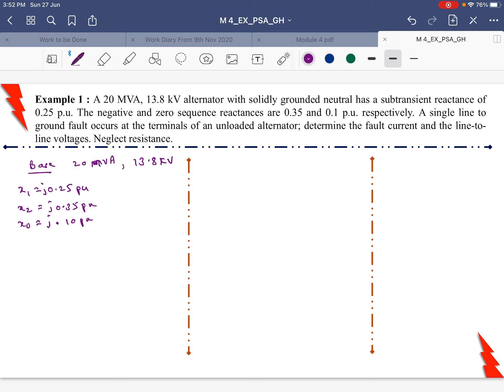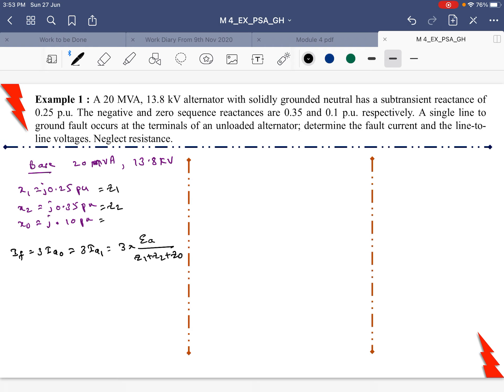Next, we find the fault current using the line-to-ground fault formula: If = 3·Ia0 = 3·Ia1 = 3·Ea / (Z1 + Z2 + Z0). The values of Z1, Z2, and Z0 are given as reactances. Since only reactances are provided, Z1 = j0.25, Z2 = j0.35, and Z0 = j0.10 per unit.